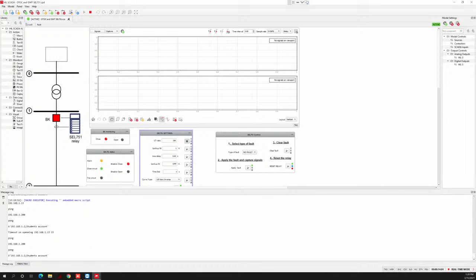You will do the same in your practice. You will send your settings to the relay, and the relay will be ready. Did you hear the tick tick? It is the relay saying that the setting was written correctly on the relay.